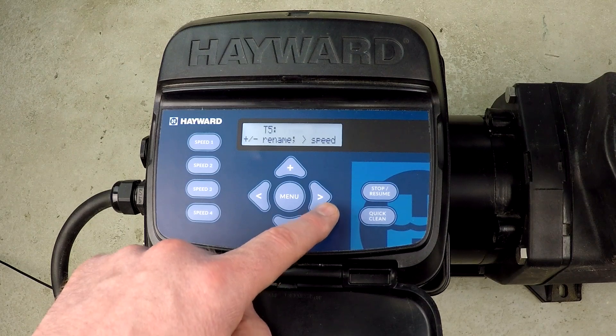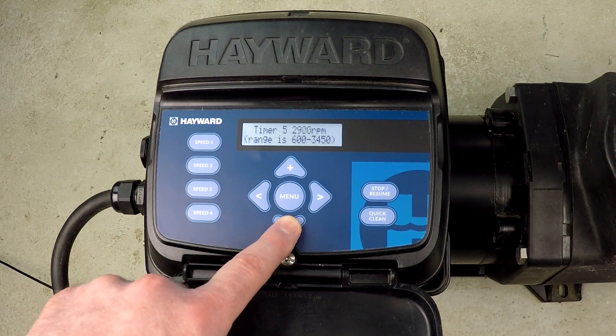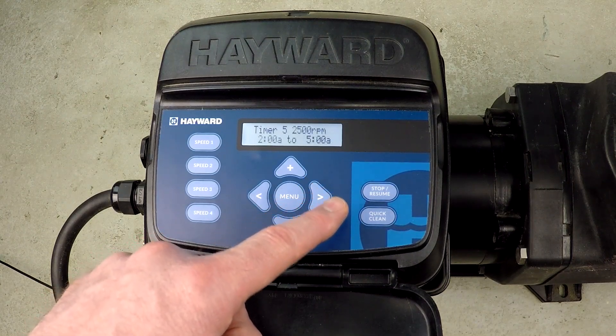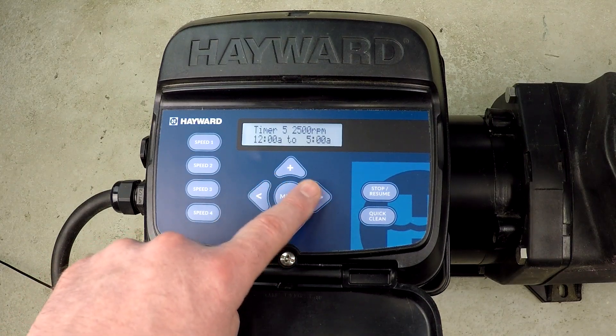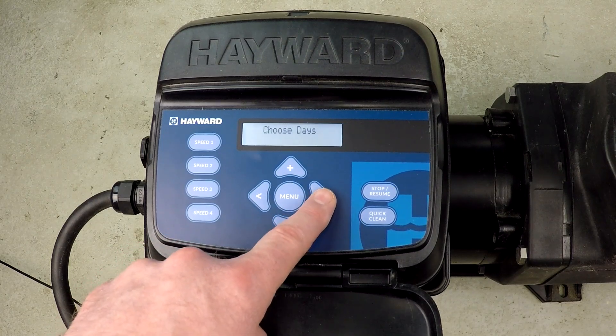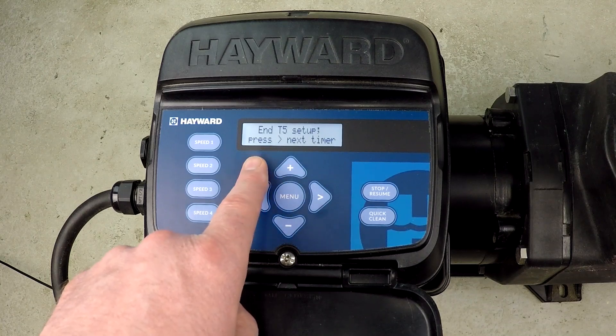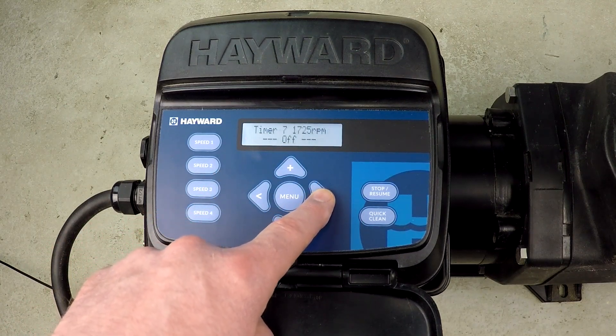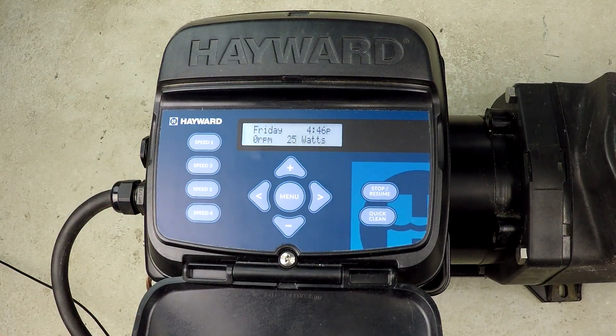Now we're in timer 5. I want to change the RPM back down to 2,500, and set it to run from midnight until 5 a.m. That completes my 24-hour dynamic schedule. I hit advance for 7 days a week. Timers 6, 7, and 8 are all off. Press menu, then press the plus button to save the programming. Once saved, the pump will restart at the new programming we've just entered.